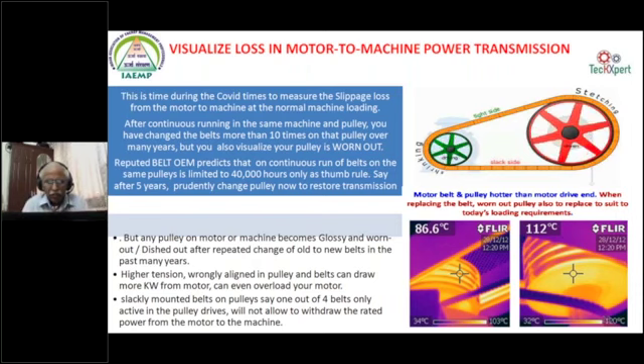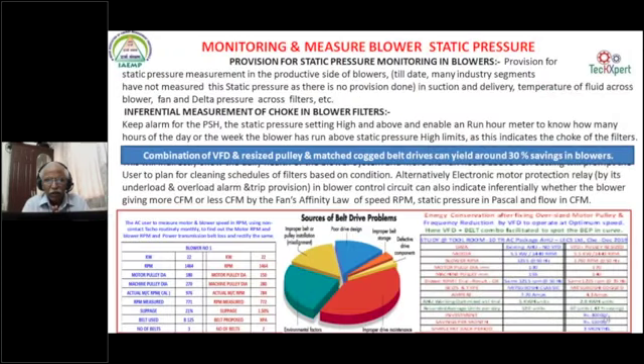You can see, especially on the blowers, a 100% replacement with electronically commutated blowers is easy, but it is a very costly affair. On your existing blower, it is a low cost retrofit. A combination of VFD and a resized pulley on a given blower can bring power savings of almost 30 to 40%. This power saving is achievable in all the air handling blowers and all variable torque loads. A blower itself is a variable torque load. It can be utilized in all industry utilities.